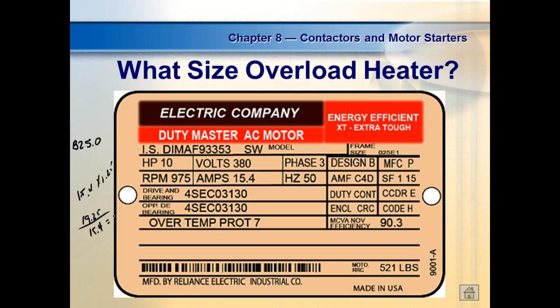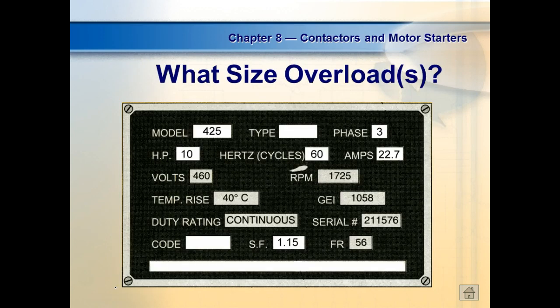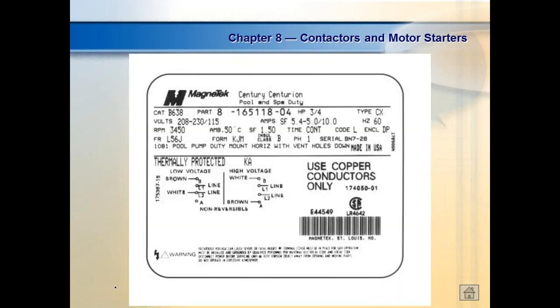Yeah, I need to go back and recheck this and check the overload. Because what we're doing is we're multiplying the number by 1.25, then we're dividing it by the number, and the answer is always going to be 1. So I need to go back and check where that came from. I don't know where it got messed up at. So right now, let's just choose the overload between there, and I'll go back and check where that came from. So what about this guy right here?